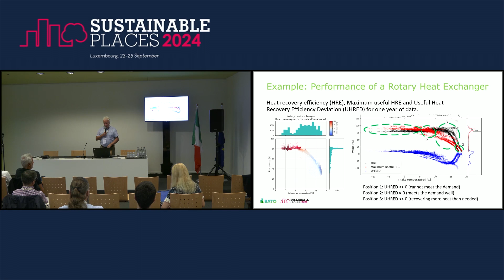In area 2, you can see there's a good correspondence, and in area number 3, the actual recovered heating energy is much higher than what is useful. This means the control of the rotary wheel is not optimum—we are recovering more heat than we need. This may result in increased temperatures in the spaces, or an increased cooling need in some systems. So it's quite easy to identify problems here, and you can start figuring out how to solve them just by looking at an overview curve like this.